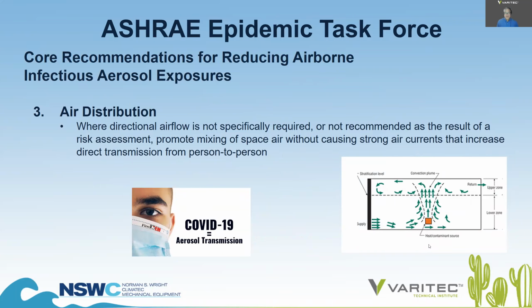Air distribution, one that we really do consider very carefully. ASHRAE advocates as a core recommendation that where directional airflow is not specifically required or not recommended as the result of a risk assessment, promote mixing of space air without causing strong air currents that increase direct transmission from person to person. The illustration shown here suggests, well, what about displacement ventilation? In my mind, it seems to conform completely with ASHRAE's core recommendation on air distribution.